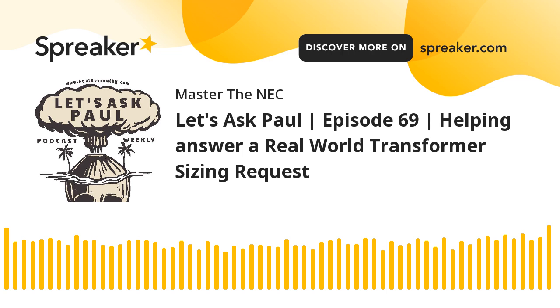Okay. Remember, the load is still 78 amps. And that nameplate has already been derived from the values that are in 440. So it's already done. We're just choosing the nameplate. Remember, no different than what you would do if you were sizing this for service or something like that. No different. Okay? So again, knowing what our loads are, that's how we're sizing everything. Okay? And we need to know what that transformer can handle.